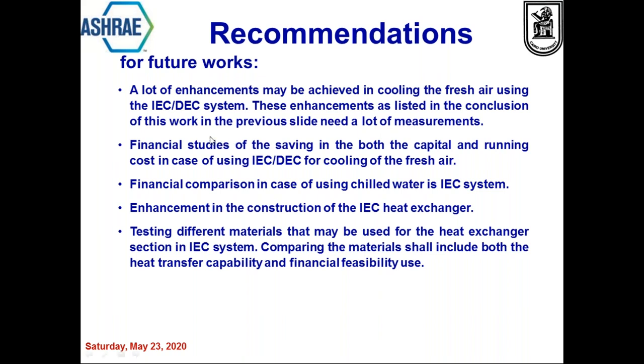So for our future work, with these recommendations, we are doing financial investigations to look into the savings in both the capital and running cost of the system, because we have the pumps for the sprayed water, and we have the energy for the humidifiers, and we have the power for the fans. And all of this has to be considered in your life cycle cost analysis. Testing different materials that can be used for indirect evaporative cooling is very important. We have to look into the heat transfer capabilities and also the financial feasibility of using these systems.